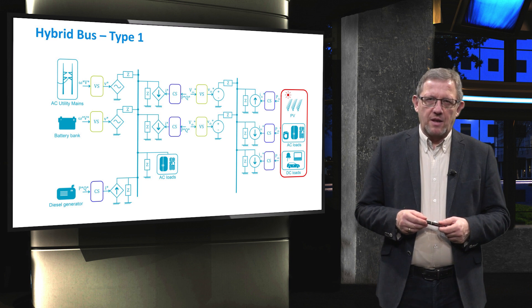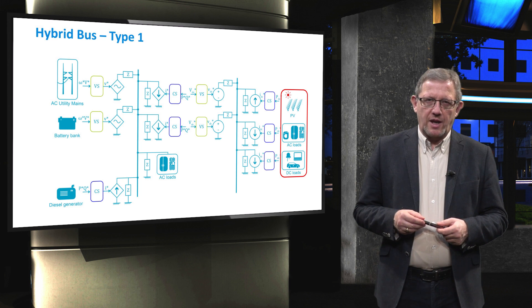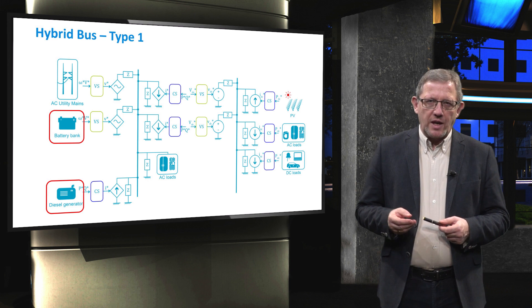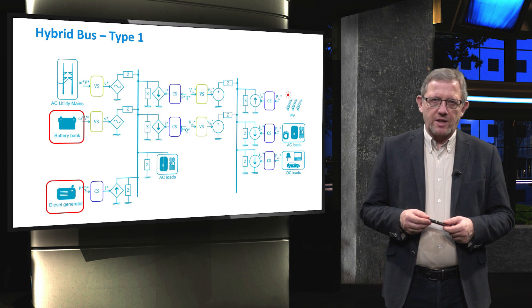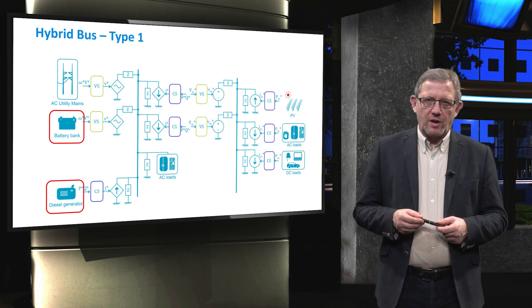At the AC bus, if strong, the grid is typically the best choice to control the AC link voltage. However, if the grid is weak, then the battery bank or diesel generator can be used to regulate the AC voltage.